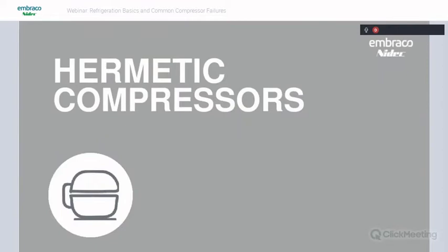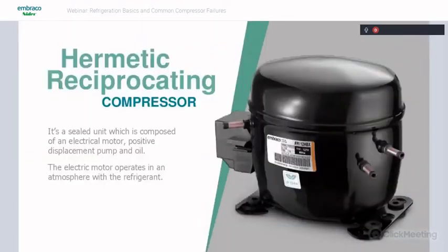So moving on to hermetic compressors. What is a hermetic compressor? It's basically just a sealed unit, which is composed of an electrical motor, a positive displacement pump, and the oil. And the electric motor also operates in the same atmosphere as the refrigerant, as refrigerant suction gas is usually used to cool the motor, along with air drawn across the shell by the condenser fan. So basically, these are sealed. You cannot open them up for service.